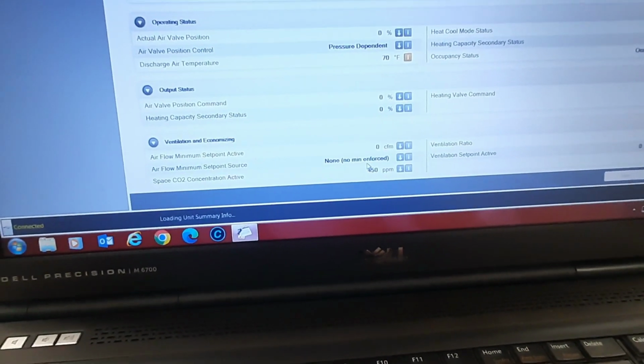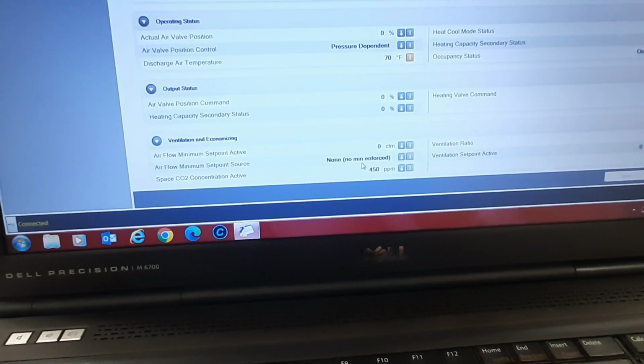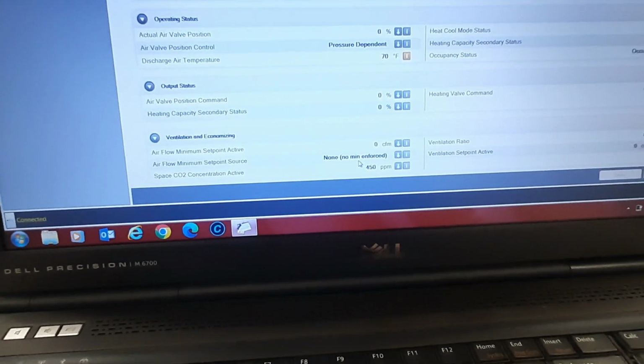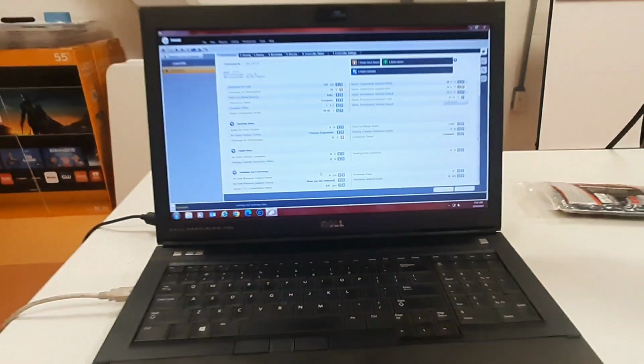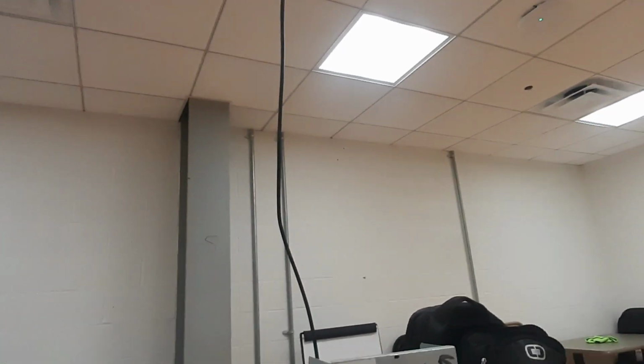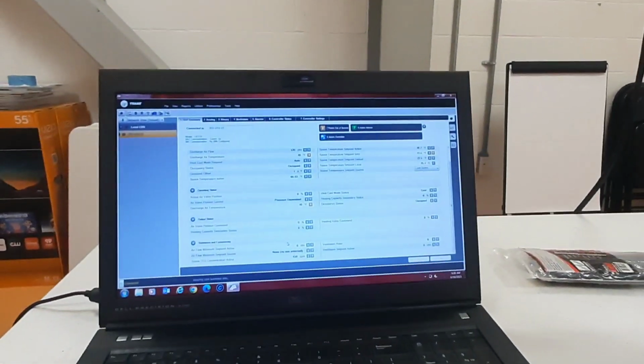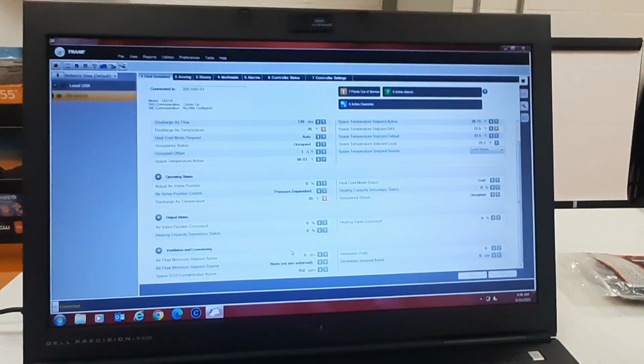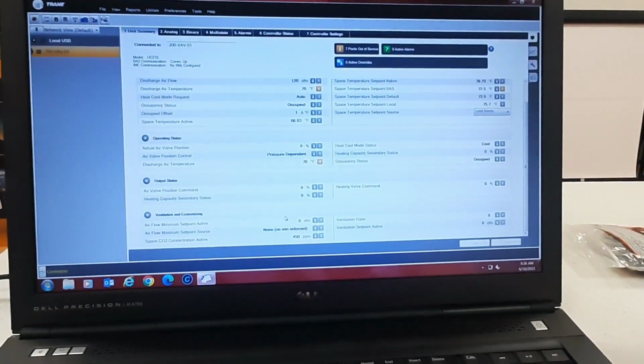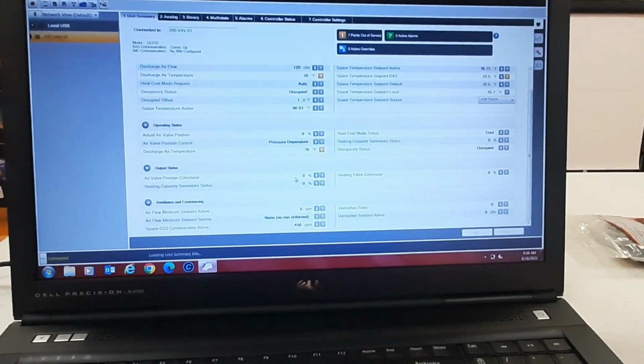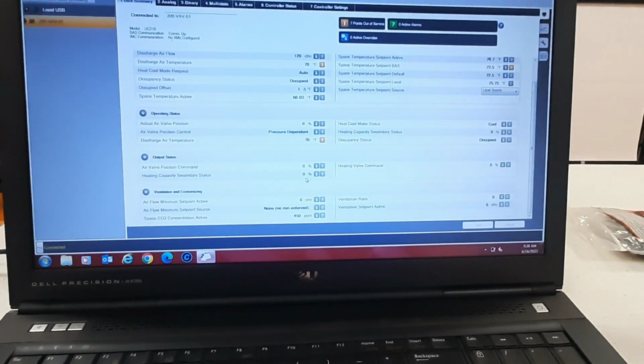So there's no min position enforced. We will set a minimum on this. What I want to do is drive it open, see how much CFM I get out of it, and just make sure the airflow noise isn't too much. They want this room cold, so I don't think we're gonna bother them too much with airflow, but this thing ought to dump a whole lot of air if I can ever get it open.